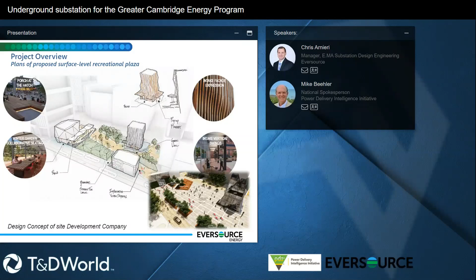From there, then we had to start thinking mechanical protection systems, really building in. And this was, again, kind of things that we learned from our outreach to the other utilities that have these below grade substations. We did bring some of our own flavor for our own protection system or different mechanical protection systems as well. But we first started off with a blast overpressure, knowing that the transformers were going to be oil filled. TEPCO is a big fan of, or not big fan, but they do utilize gas insulated transformers. We looked at it. We've never used them before in the past. Physically, they didn't quite fit in the spaces that we had available for them. So we stuck with oil for that reason.